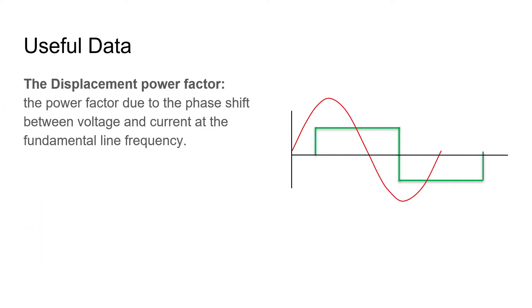The displacement power factor. It is defined as the power factor due to the phase shift between the voltage and the current at the fundamental line frequency. Mathematically, it is cos of the distance in degrees from the zero crossing of the voltage and the current wave. That is, cos of alpha.